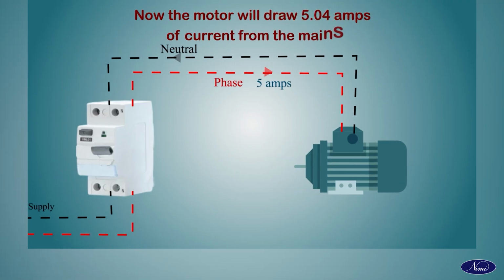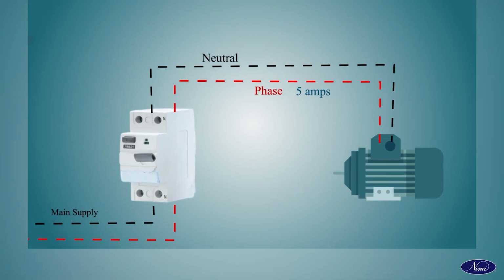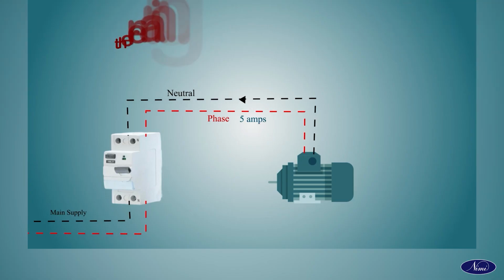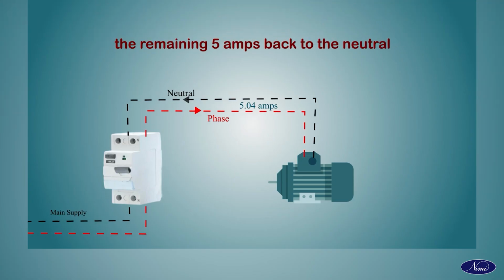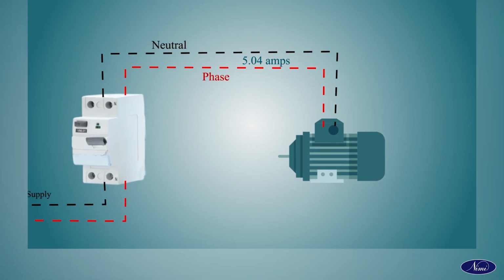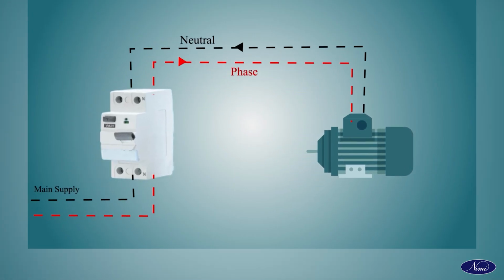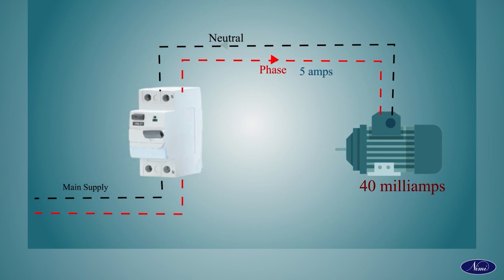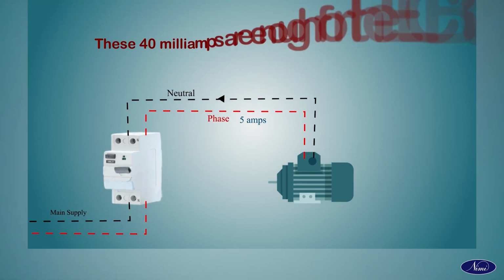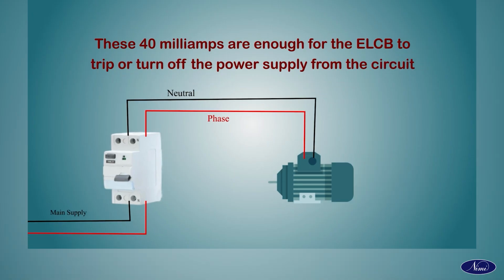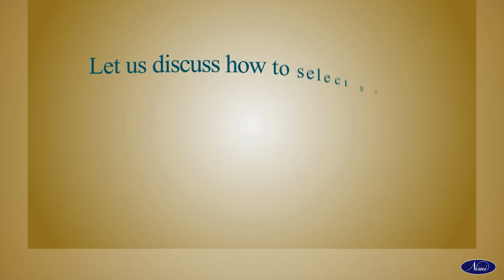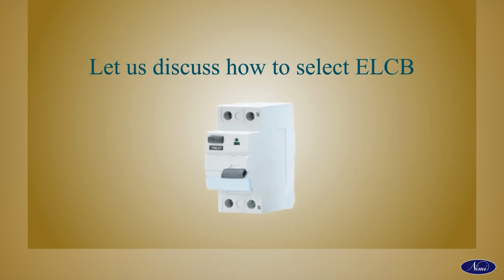Now the motor will draw 5.04 amps of current from the mains, in that the outer body of the motor takes 40 milliamps and the remaining 5 amps go back to the neutral. Here, a current difference exists between phase and neutral of 40 milliamps. These 40 milliamps are enough for the ELCB to trip or turn off the power supply from the circuit. Let us discuss how to select an ELCB.